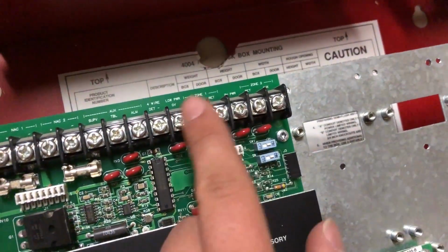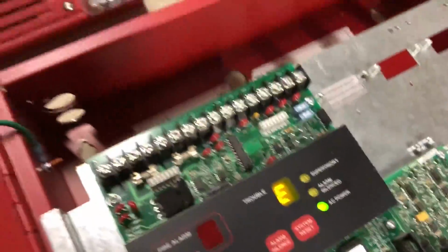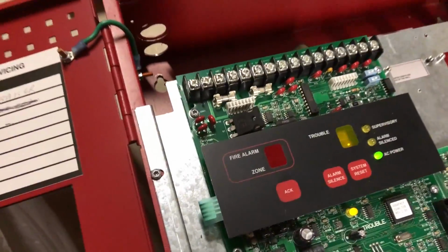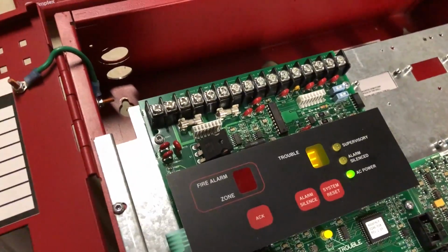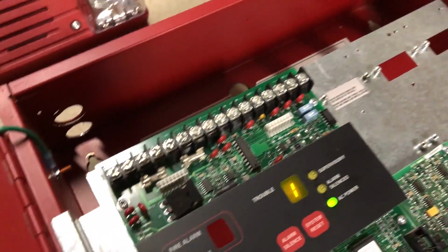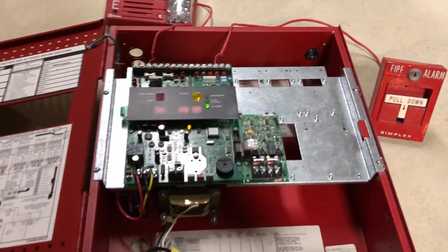As for our zones, for smoke detectors, they do the same thing. They operate on 24 volts DC, but upon an alarm, it causes an increase in current that the panel sees the same way it would see a pull station. So I hope that information is helpful enough. Now, to give a demonstration of that and kind of talk about it, I will set up some devices here and we'll make some noise.